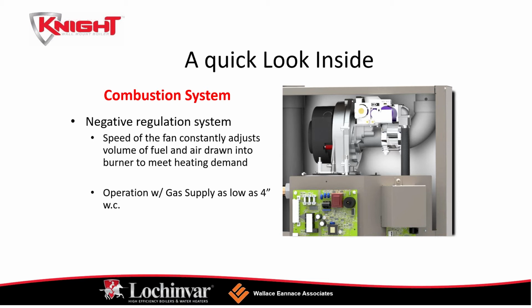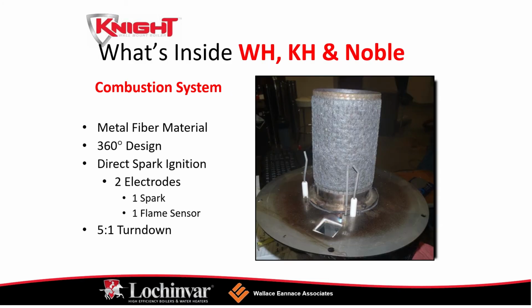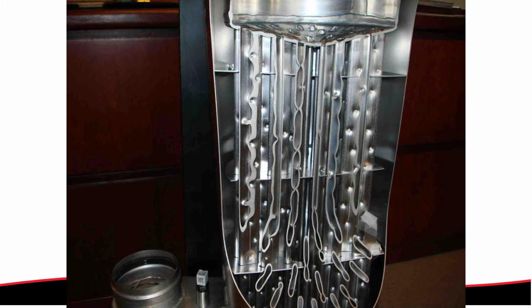And we're rated at 145 psi on our 286,000 to 800,000 BTU units, and we're rated at 60 psi on our smaller 80 to 286 BTU units. More of a look inside the combustion system, negative regulation system. So the speed of the fan adjusts to the volume of fuel and air drawn into the burner. And again, as stated in the video and in the slide earlier, the operation will work on gas supply as low as 4 inches water column.